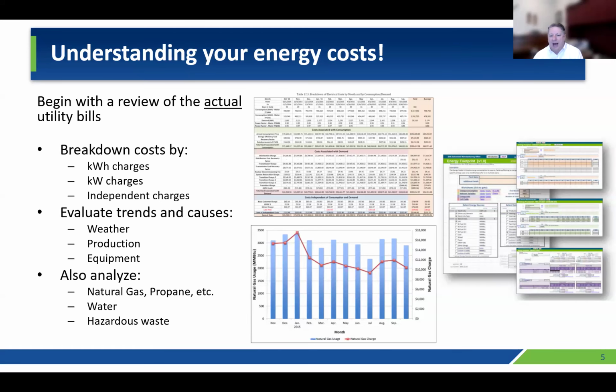What you want are the actual utility bills, because on those bills there will be a breakdown of how much you're being charged, not overall, but how much of your charges are coming from kilowatt hour usage versus peak demand kilowatt usage. And we'll talk about that in a moment, as well as what charges are independent of how much energy or power that you are using.